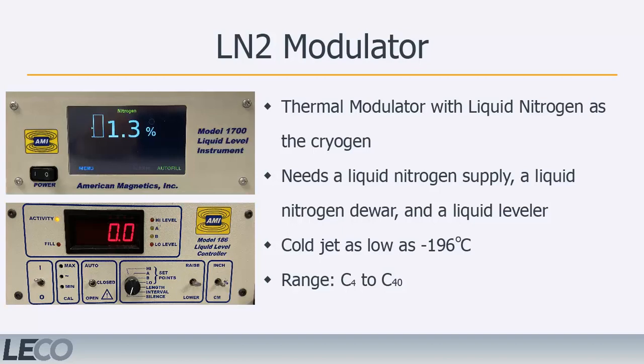The LN2 system can obtain cold jet temperatures as low as negative 196 degrees Celsius and effectively cryofocus compounds with a volatility range between C4 and C40.